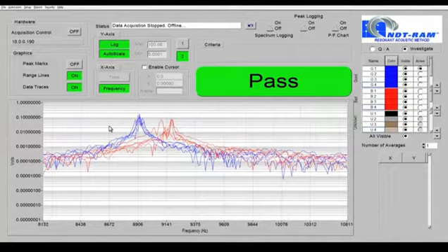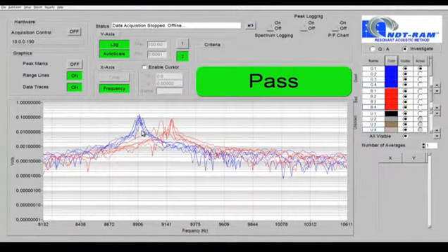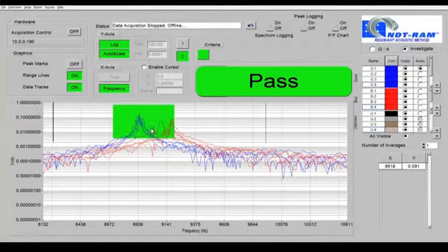As you can see, there are several red peaks for bad parts that are separate from the cluster of similar blue peaks for good parts. Add criteria to the blue peaks by right-clicking over the peaks and clicking on Add Criteria. This will add a green criteria box and range lines.